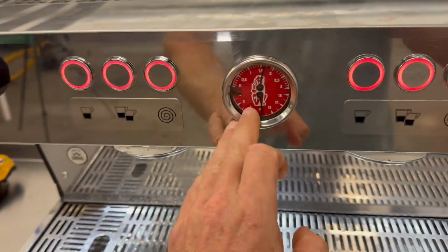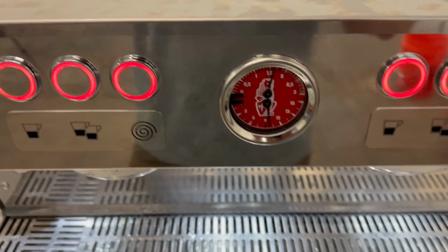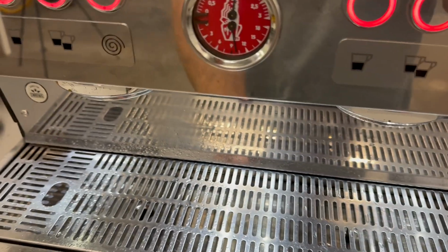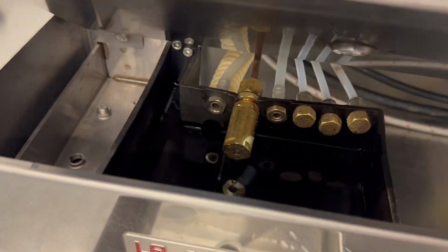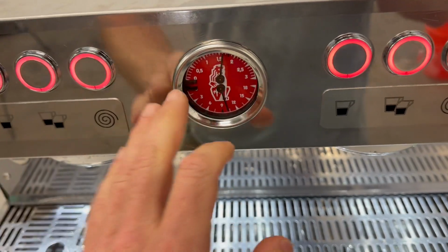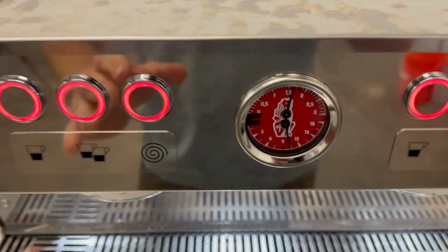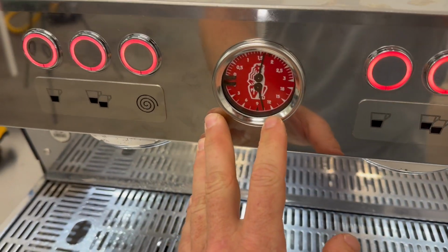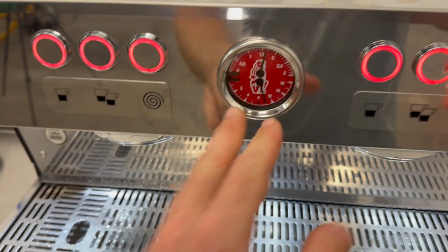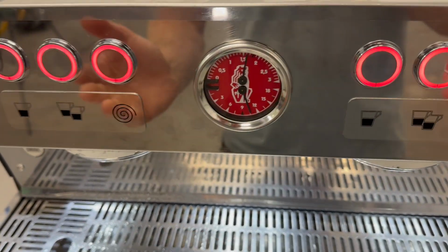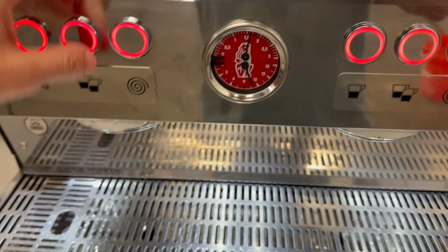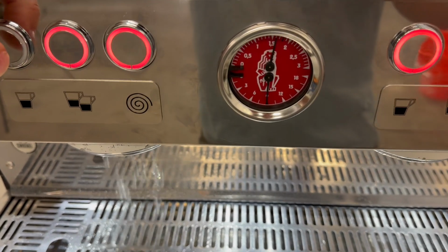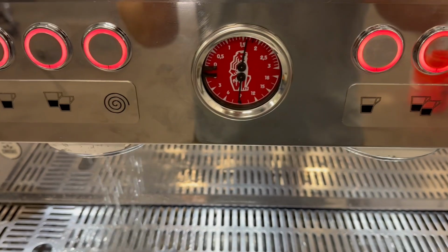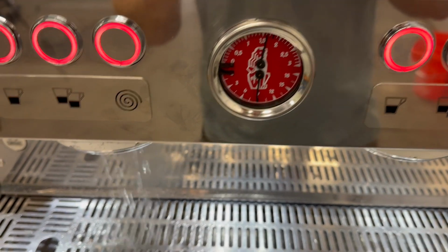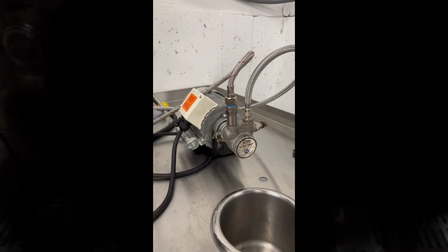If you're not getting 9 bars of pressure when you're pulling a shot, do not try to adjust the expansion valve. That's not gonna change that. You have to adjust the pump, and vice versa. If you're not getting 12 bars of pressure, don't adjust the pump, because then you're just gonna mess with the shot quality and it's gonna get super wacky. So 9 bars of pressure when you're pulling a shot, right? Every time. And now we can talk about the pump real fast.